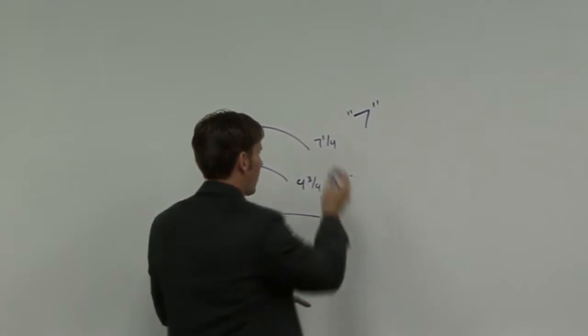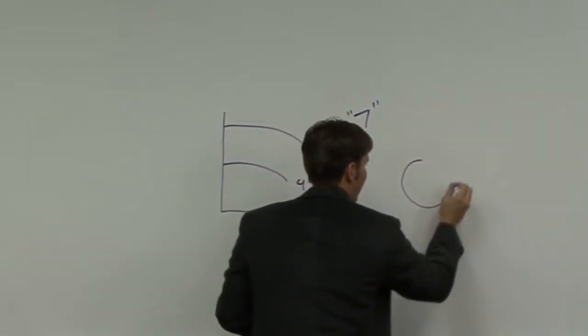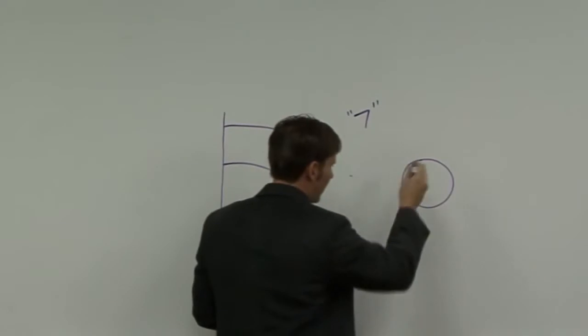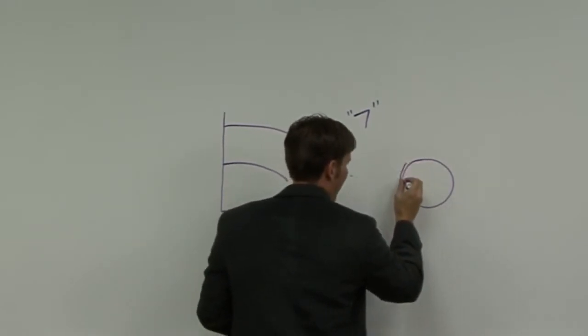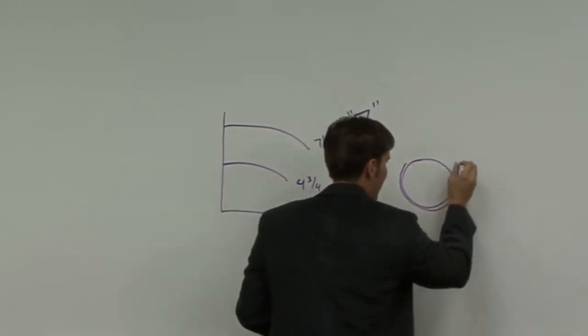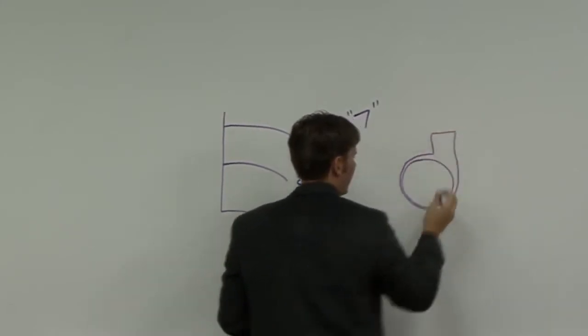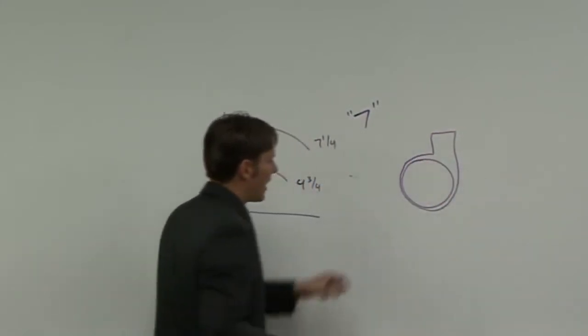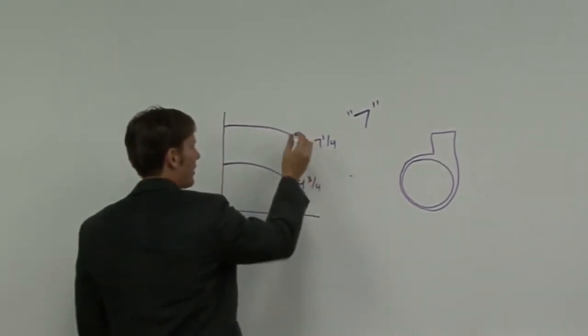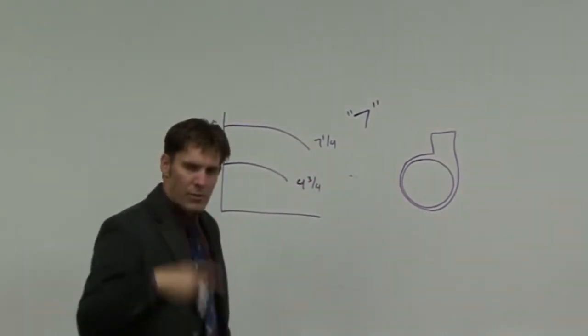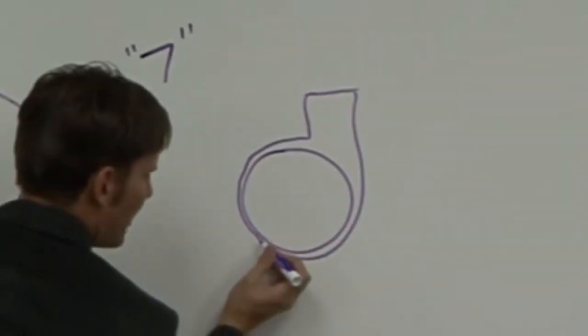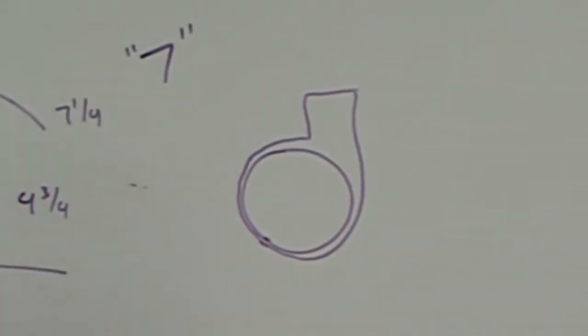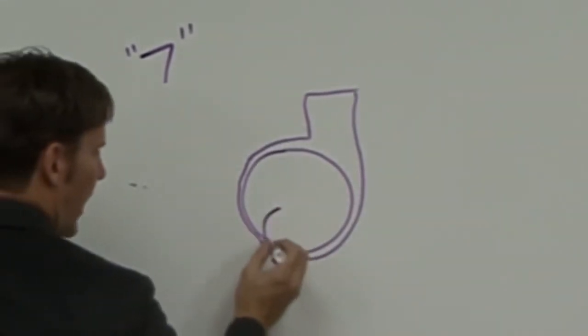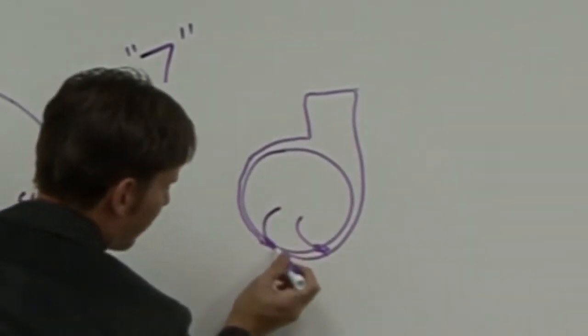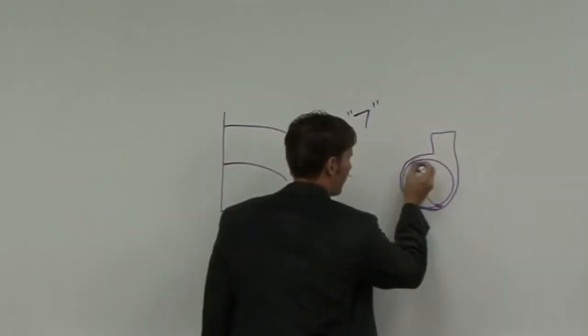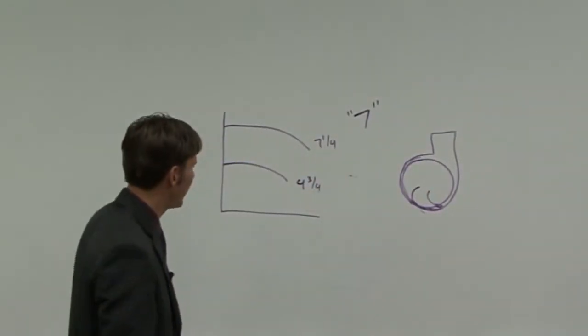So what this is doing is I've got a 7 1/4 inch diameter can or impeller inside, and then I've got very narrow spaces between the two cans. So I can't fit an impeller any larger than that because I simply don't have the space. This is the largest impeller trim that I can use. As we get into efficiencies, I want you to understand, look at the distance between this wall and this wall. The distances are so small that as I rotate the water out of this can, there's no room for it to turbulate around. It just moves fluidly through here. So we're going to talk about that when we get into efficiencies.